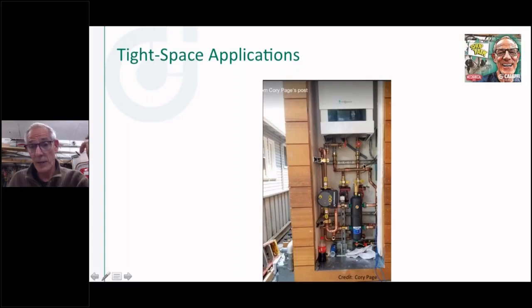Can you imagine if he had to do a primary, secondary loop and get closely spaced tees for the boiler, closely spaced tees for his distribution, closely spaced tees for his secondary pumps? That would take up quite a bit of real estate, and that room's got to be 3 feet at the most wide by the looks of the boiler and all the stuff. So a great job, and he made it look nice too, cramming all that stuff in there.